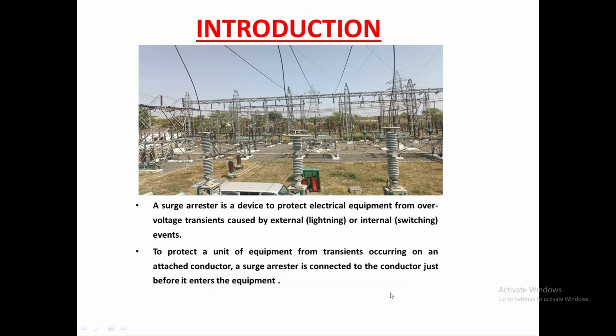A surge arrestor is a device which is used to protect the electrical equipment from the overvoltage transients that are caused due to lightning or internal switching events. To protect the valuable equipments from the transients occurring attached to the conductor, a surge arrestor is connected to the conductor before just entering into the equipment. That may be a transformer or other high voltage equipments.